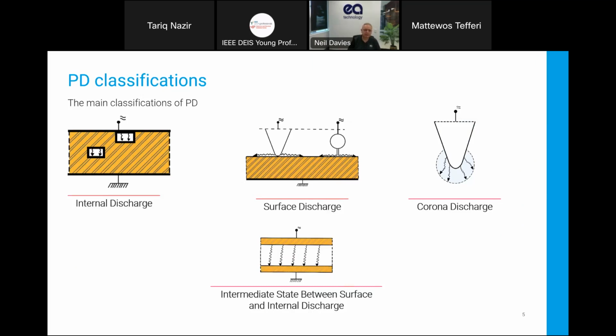classifications of partial discharge would be internal discharge. So that's simply stuff that's happening deep inside the insulation. So this could be, as we can see in the diagram here on the top left, we can have it in the center of insulation. We can have it towards one of the conductors. They will give you different characteristics, but ultimately that's stuff that's happening inside.